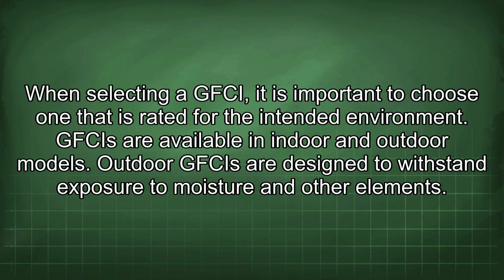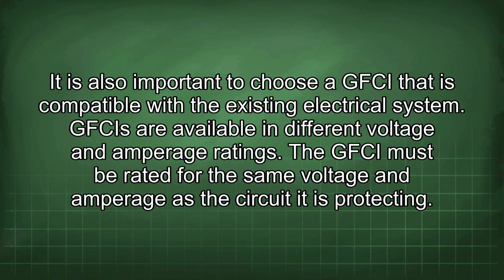When selecting a GFCI, it is important to choose one that is rated for the intended environment. GFCIs are available in indoor and outdoor models. Outdoor GFCIs are designed to withstand exposure to moisture and other elements. It is also important to choose the GFCI that is compatible with the existing electrical system. GFCIs are available in different voltage and amperage ratings. The GFCI must be rated for the same voltage and amperage as the circuit it is protecting.